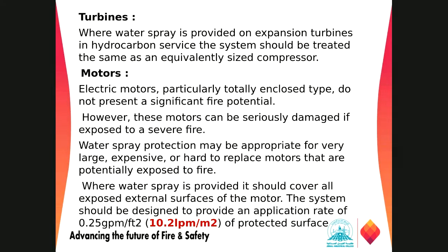And we need it for the turbines also, right? I think someone discussed during the water mist application, can we install the water spray system for the turbine? Yes, we can install it in the turbine area also, where water spray is provided on expansion turbines in hydrocarbon service. The system should be treated the same as the compressor, right? So based on those, we need to install water spray systems in those areas.